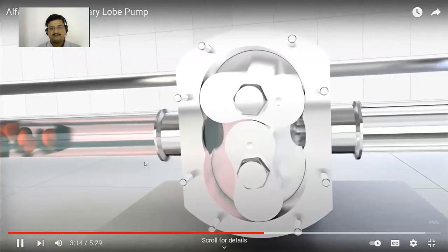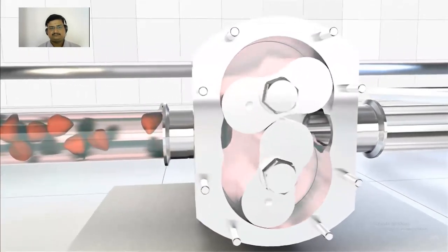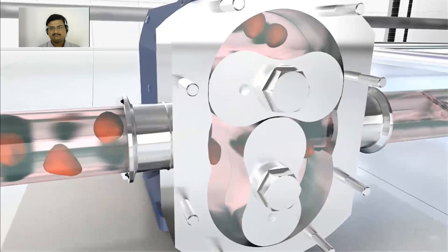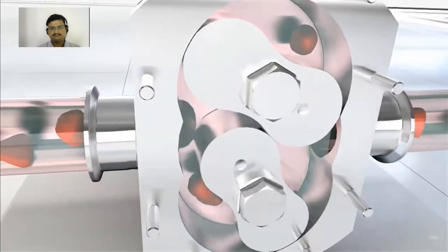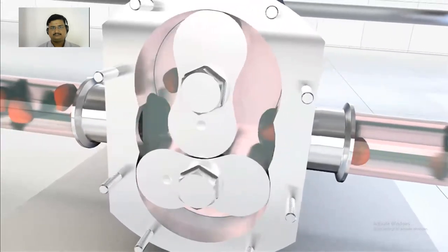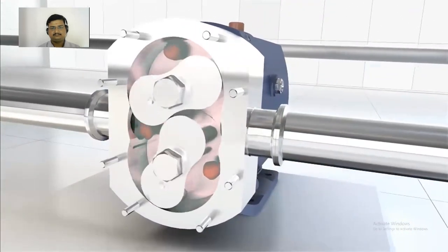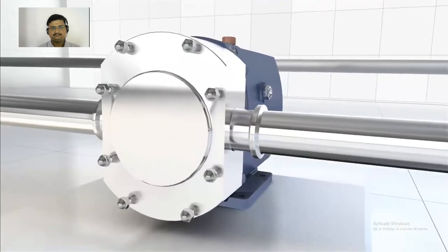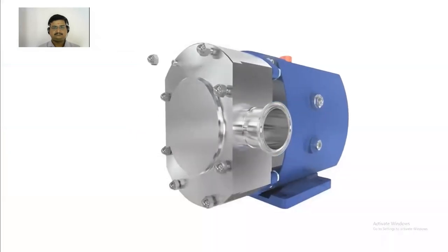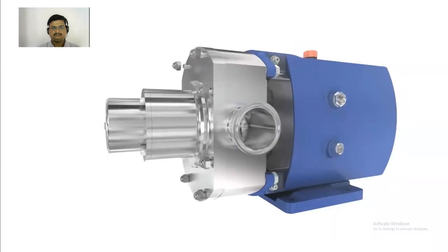Containing solids with minimal damage. So here pumping is going on, and that's why they have used the bi-lobes. Improved volumetric efficiency when transferring low viscosity liquids, the bi-lobe rotors are also available in non-galling alloy. This allows closer pump head clearance and reduced slip. Among the other options available are the integral relief valves, jackets and saddles, and a rectangular inlet.